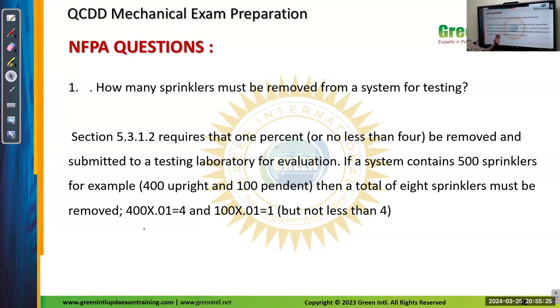Minimum 4 pieces required for one type of sprinkler and required from another type of sprinklers. For 1,000, it will come 10 sprinklers should be removed on site. Yes, if it is 1%, it is 10 sprinklers. But if this 1,000 pieces is the same sprinkler, you should remove at least 4. So you are taking the maximum of this. Means you have to replace the 10.